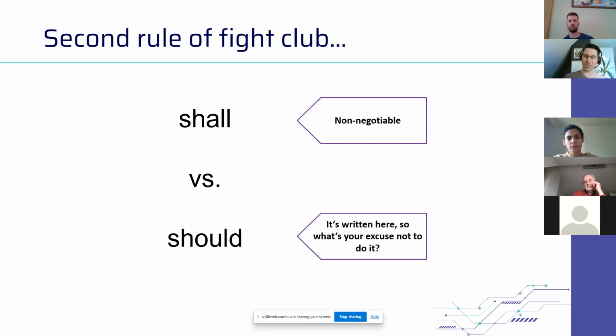Of course, you can avoid that if it's not applicable to your device. For example, if you don't have a tangible product like a pen or something, biocompatibility probably doesn't really matter, especially for software. But if you have something that requires biocompatibility assessment or hygienic requirements, disinfection, then this shall requirement applies. Period. It's non-negotiable. If you don't implement it, and you don't have a trail in your quality management system, you have no evidence that you made an assessment and implemented this requirement. The very moment, you have a non-compliance.